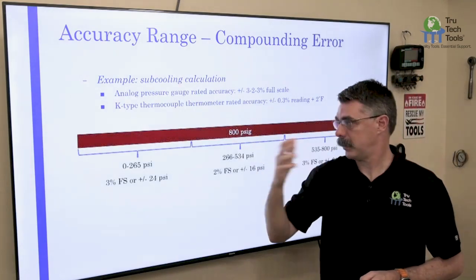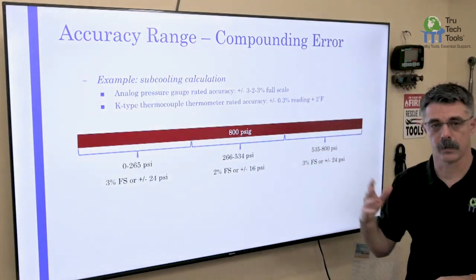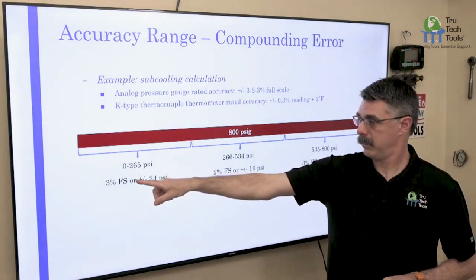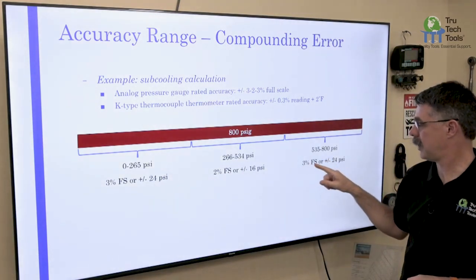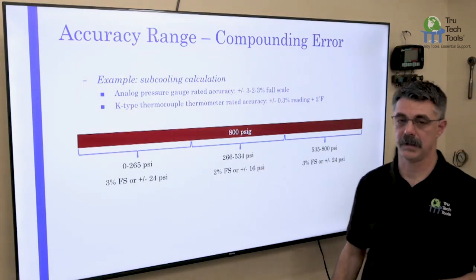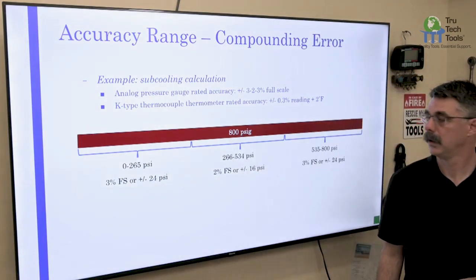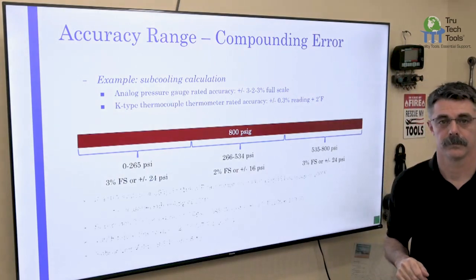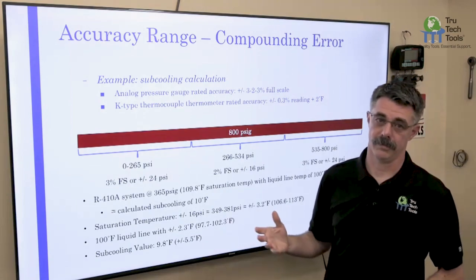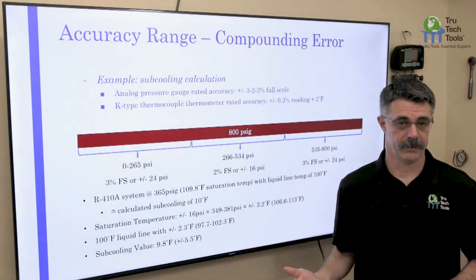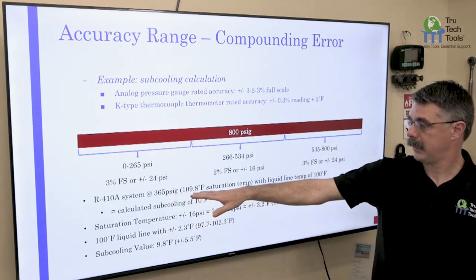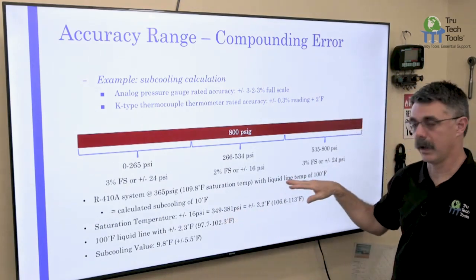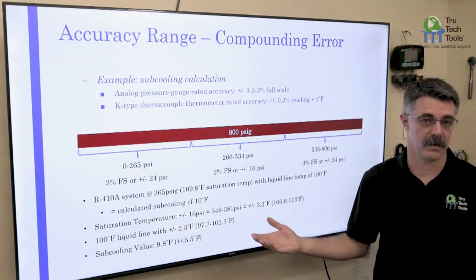For a typical 410A pressure gauge with an 800 psi high-side range, in thirds: the ends are plus or minus 24 psi (3%), the middle is plus or minus 16 psi (2%). Taking a 410A system at 365 psi gauge, that's 109.8°F — call it 110°F saturation temperature. With a liquid line temperature of 100°F, our calculated subcooling is 10 degrees. That's easy math.